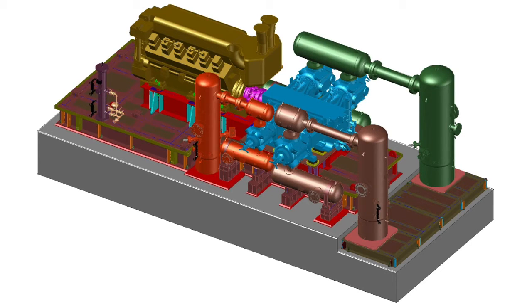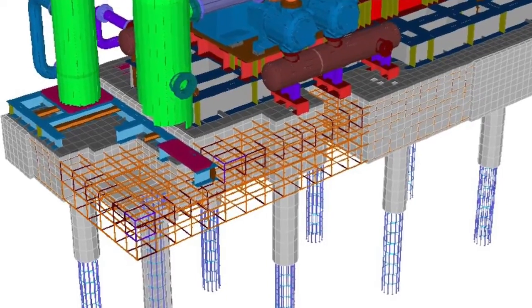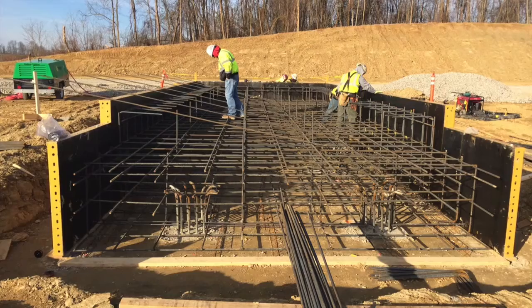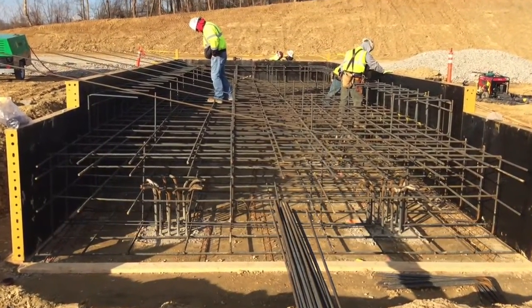The acoustic solution integrates the scrubbers, cylinders, bottles, process piping and coolers. Properly sized and strategically placed pipe supports ensure lower vibration of the piping system. During the foundation design, we specified additional reinforcement steel to transmit and dissipate the energy from the unbalanced forces. The additional steel significantly reduced cracking in the high-stress areas of the main foundation.